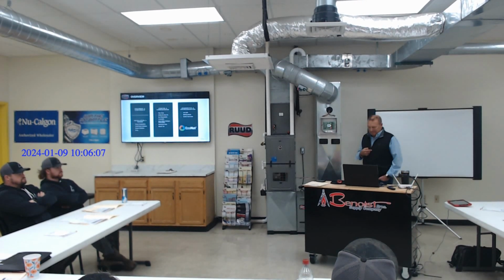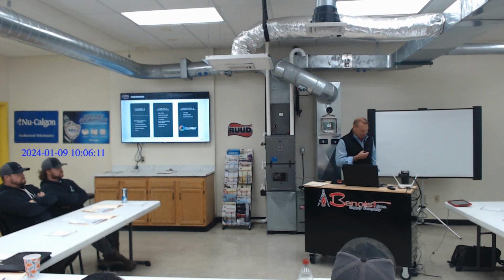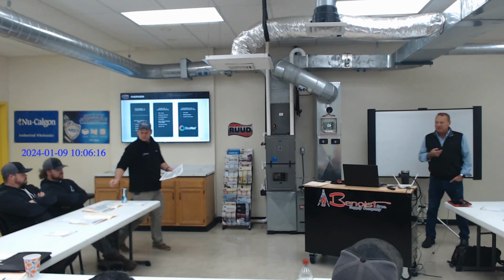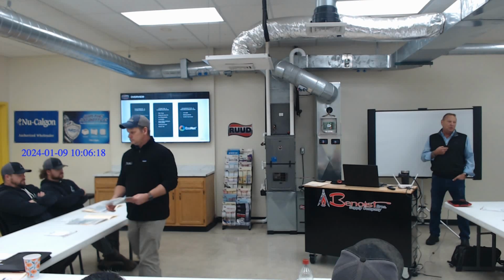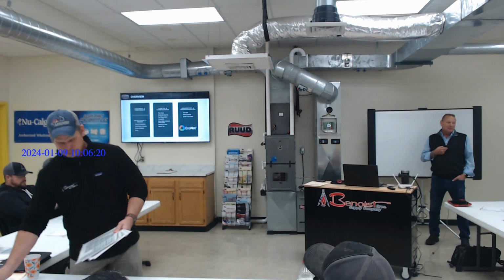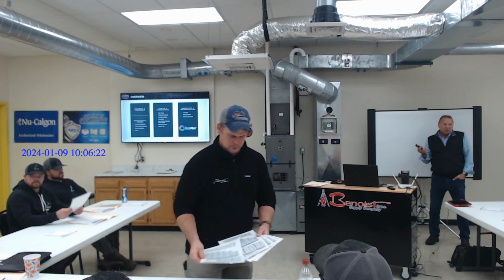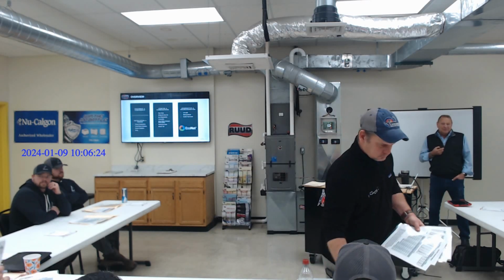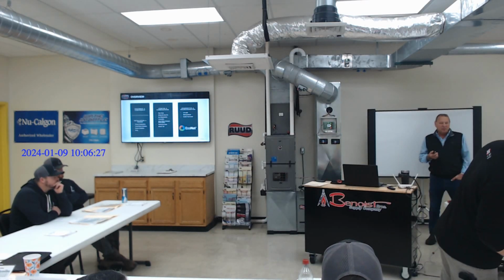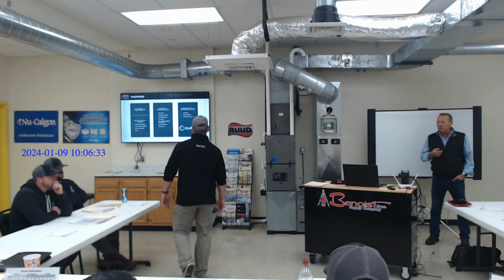So if you don't know how to use a duct calculator and you want a rough figure, and I don't like rules of thumb, but if you figure 75 or 80 square inches per ton of cooling on return air, and you measure all your returns and use that formula, it'll keep you out of trouble on return air, okay? I'd suggest you use a duct calculator, and that's a whole airflow class we can teach. But we have to pay attention to returns.